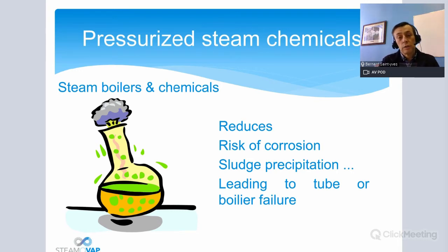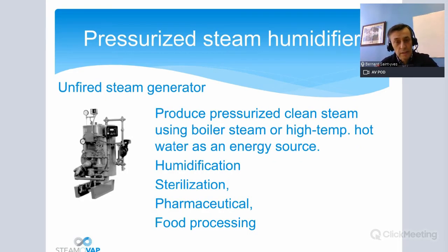Okay. So the good news is, with any problem, there is a solution. The solution is to now use a clean steam pressurized system, which is made mainly with the unfired steam generator. What is an unfired steam generator? It is a system really close to the humidifier, but it's working under pressure. So it's producing clean steam using the boiler steam or high temperature hot water as an energy source. So there is no more fire inside the unit boiling the water, but only the steam pressure from the steam boiler. And with this, they are able to avoid the chemicals.